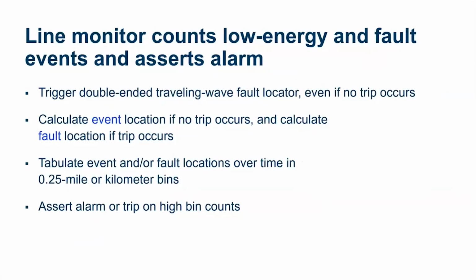As soon as they get to an alarm set point, we're going to set an alarm, and you can also set another bin to trip. So you could have maybe, if I get 3 alarms in a certain quarter-mile of the line, I'm going to alarm, and let's say if I get 5, I want to be really conservative, so I'm going to trip. What we're hoping is this gives us greater insight into the system, and we can actually detect faults, dispatch crews, and prevent faults before they occur.